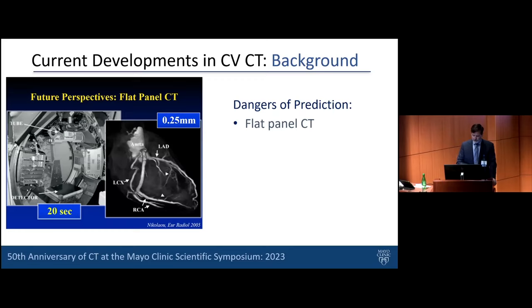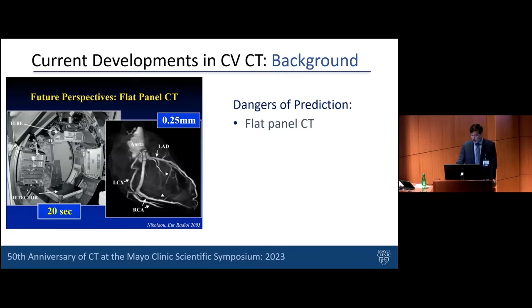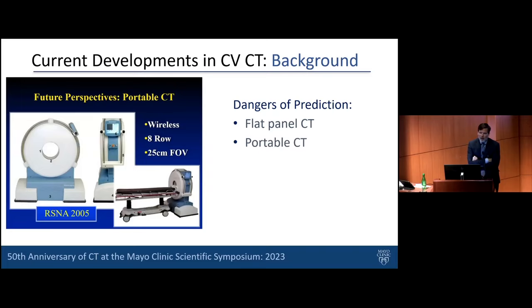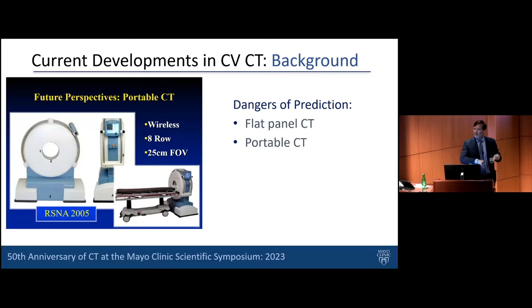The first prediction: Konstantin Nikolaou and colleagues pulled the front off a CT scanner, mounted essentially an X-ray detector, and got exquisite images of coronary arteries in a cardiac explant over about 20 seconds — not replicable in the human body. But I said flat-panel CT was coming to cardiac CT. The technology went a different direction. Second prediction: at RSNA 2005, there was a mobile CT scanner on little treads. I predicted portable cardiac CT — hook up some ECG leads and drive it around the hospital. That never happened. Both were swings and misses.